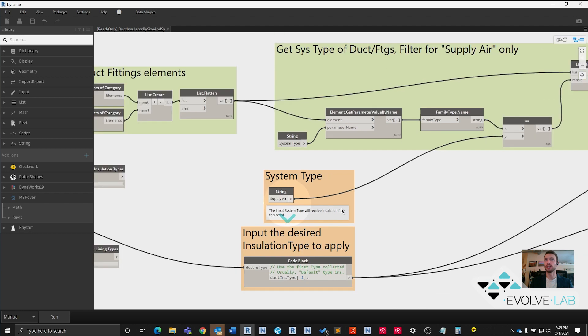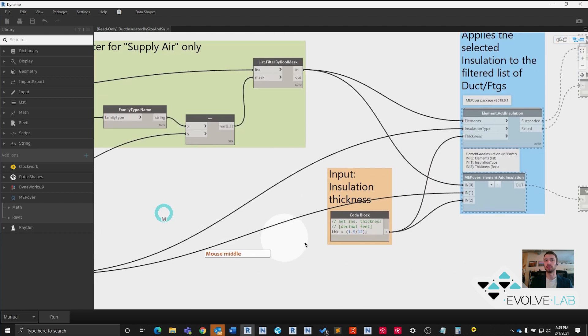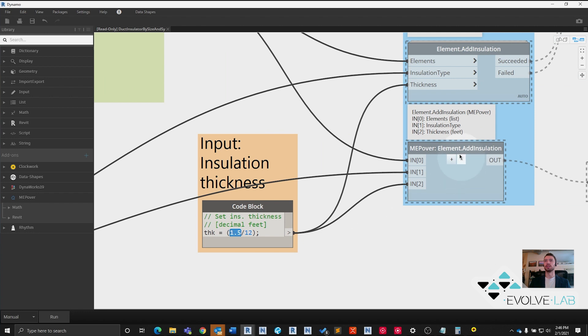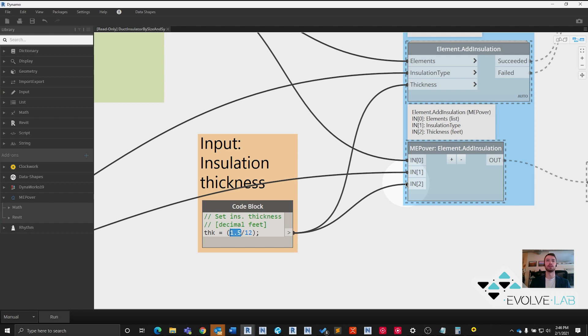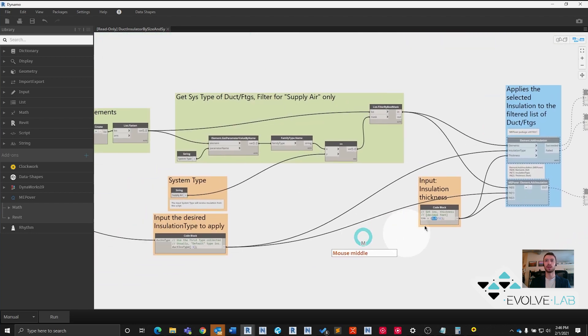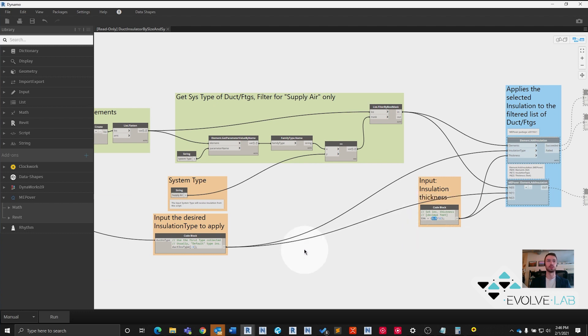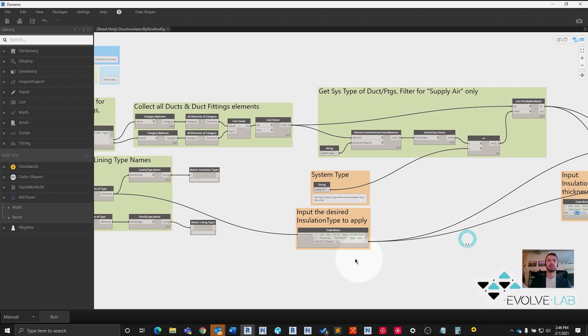We've got our supply air. Let's look at the thickness. We just saw in our duct installation schedule that we want that to be one and a half inches. Now one quick thing to note here about this MEPover node: when it accepts the insulation thickness variable, it needs to be in decimal feet. So if you put in just 1.5 and plug it in, you'll get a very thick insulation. That's not quite what you want. So don't forget to divide by 12 to get our inches in decimal feet. However you want to do that. It doesn't have to be a code block, but for visual sake, that's what we're using.